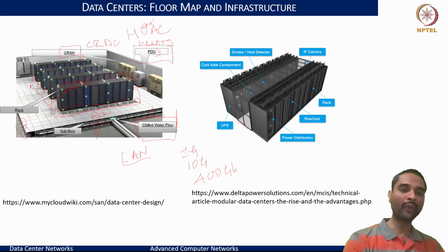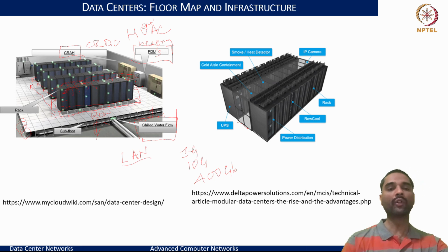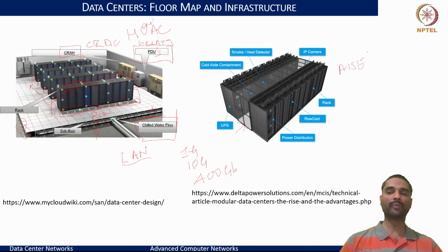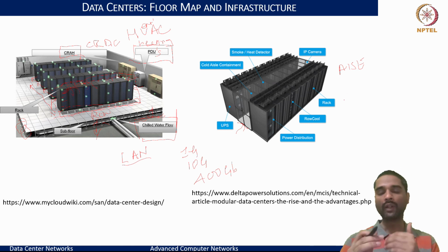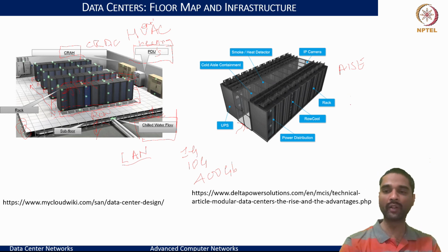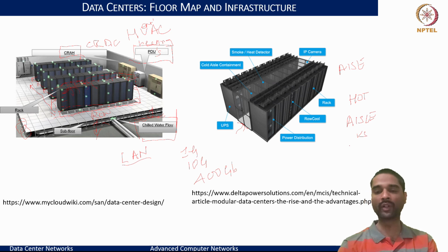And when we have such a series of racks and rows of servers, we typically call the intermediate space an aisle, which is set up for management purposes and also for air ventilation. And accordingly, if the computers are on the one side, where the heat is being generated, we may have what we call a hot aisle, versus the other side, where you would see the front end of the devices, as the cold aisle.